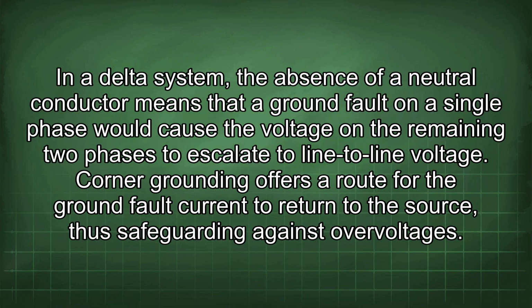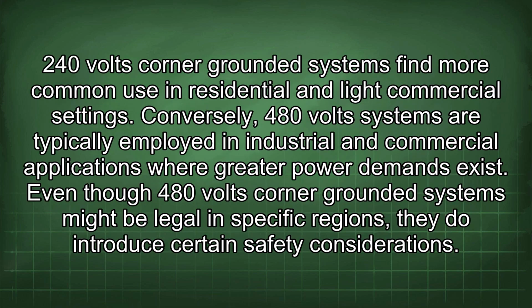In a delta system, the absence of a neutral conductor means that a ground fault on a single phase would cause the voltage in the remaining two phases to escalate to line voltage. Corner grounding offers a route for the ground fault current to return to the source, thus safeguarding against overvoltages. 240 volts corner-grounded systems find more common use in residential and light commercial settings. Conversely, 480 volts systems are typically employed in industrial and commercial applications where greater power demands exist.